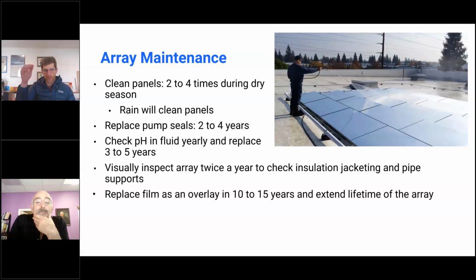There are other sets of maintenance that need to happen at longer time intervals. For example, there's a pump in the system. There are pump seals that need to be replaced. Grundfos, for example, recommends that happen every 2 to 4 years. We have the glycol in the system, which has corrosion inhibitors. We manage the pH in that system, making sure that the pH doesn't go too high. But it's replacing the fluid every 3 to 5 years.